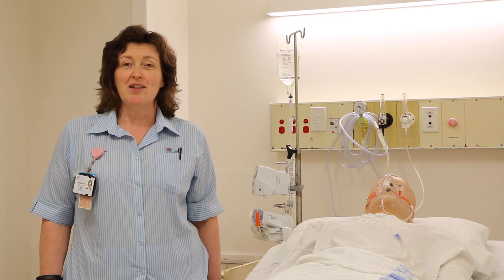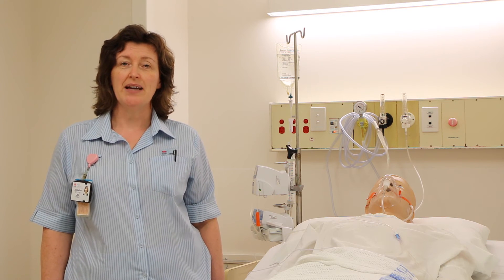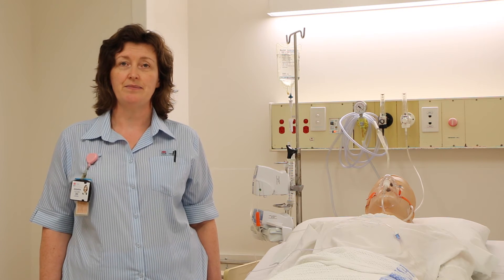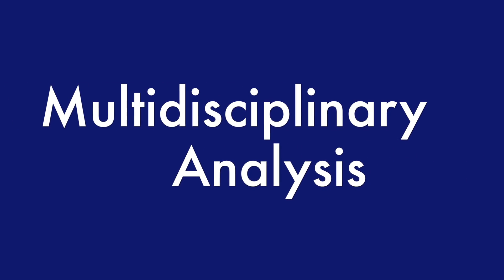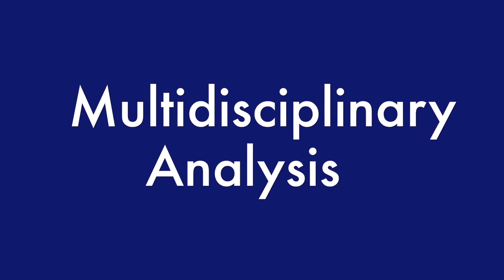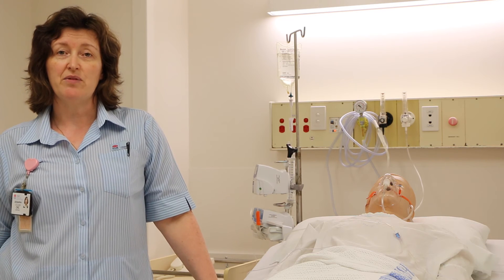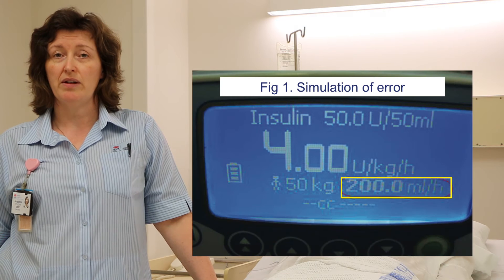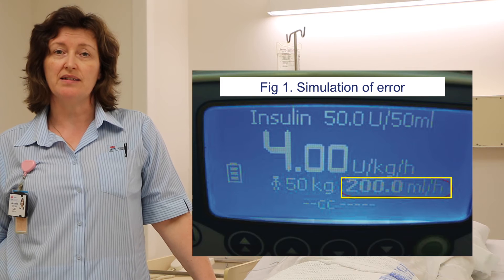The patients received immediate attention to prevent deterioration and luckily no patient suffered permanent harm from any of the medication incidents. A multidisciplinary team was formed to explore events and circumstances surrounding each incident. Analysis of the information led to a theory that the root cause of the incidents was staff inadvertently using a setting available only in the syringe driver within the dose mode configuration.